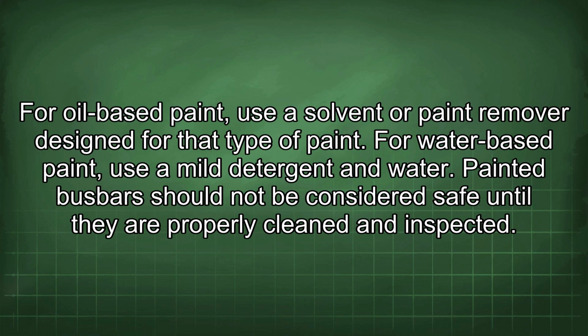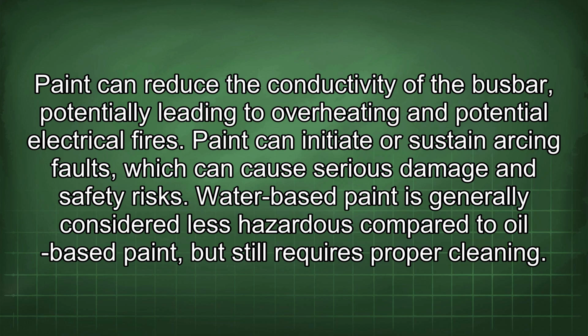Painted busbars should not be considered safe until they are properly cleaned and inspected. Paint can reduce the conductivity of the busbar, potentially leading to overheating and potential electrical fires. Paint can initiate or sustain arcing faults, which can cause serious damage and safety risks. Water-based paint is generally considered less hazardous compared to oil-based paint, but still requires proper cleaning.